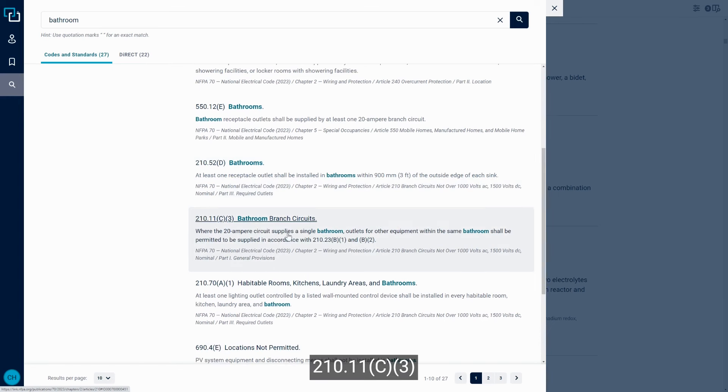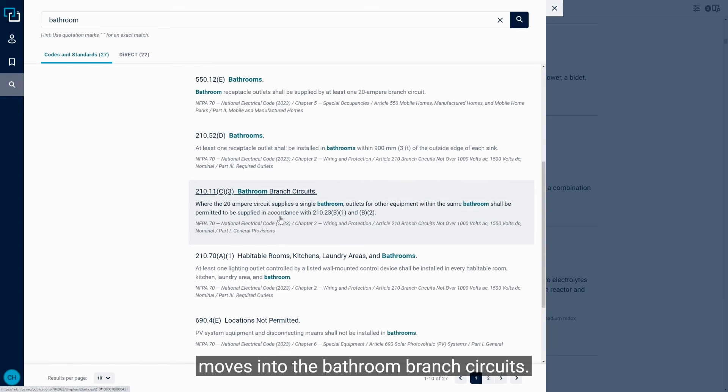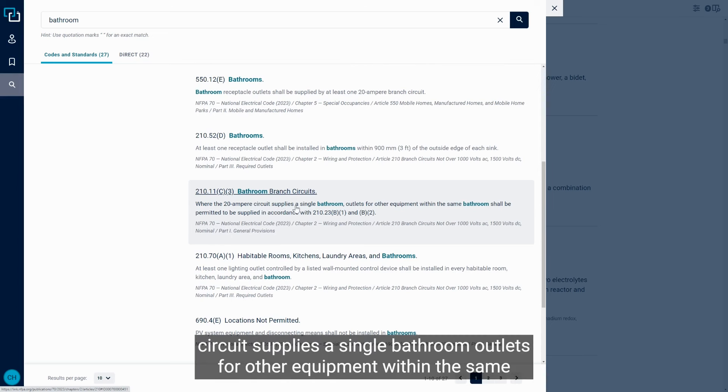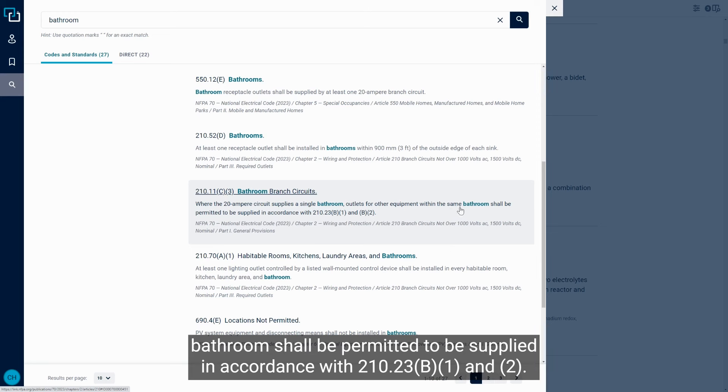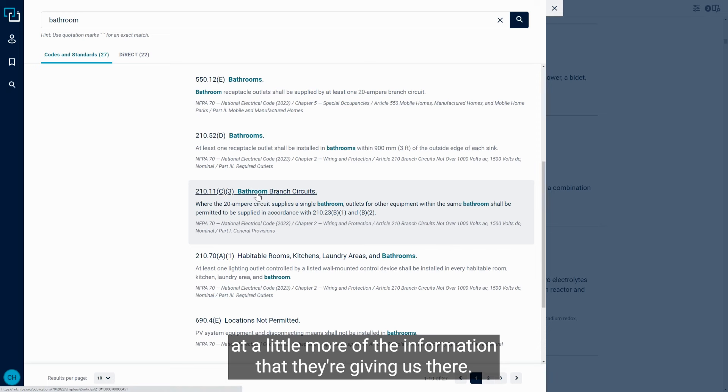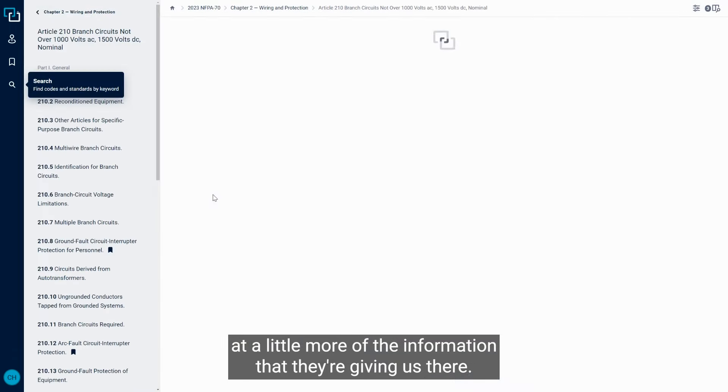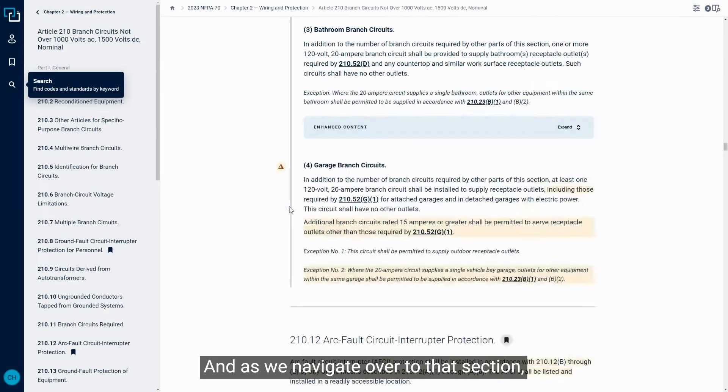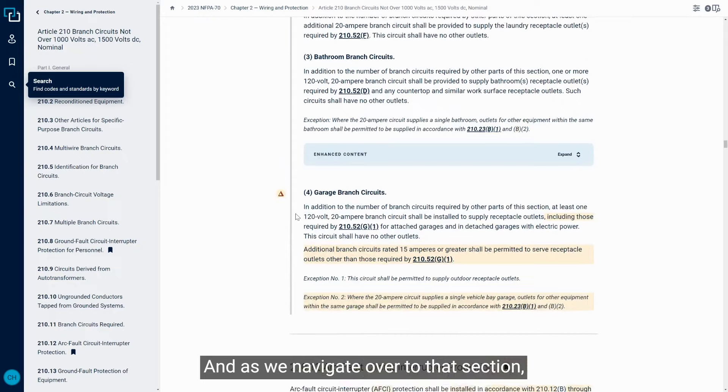210.11.C.3 moves into bathroom branch circuits. So where the 20 amp circuit supplies a single bathroom, outlets for other equipment within the same bathroom shall be permitted to be supplied in accordance with 210.23.B.1 and 2. So I want to jump into that section real quick to take a look at a little more of the information that they're giving us there.